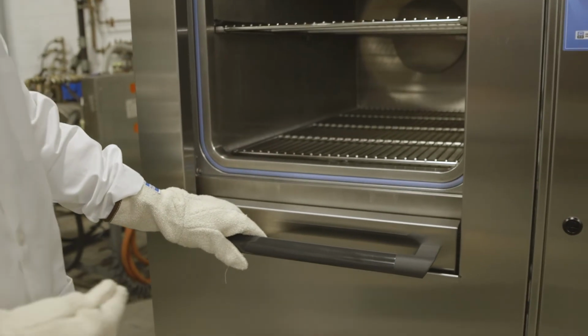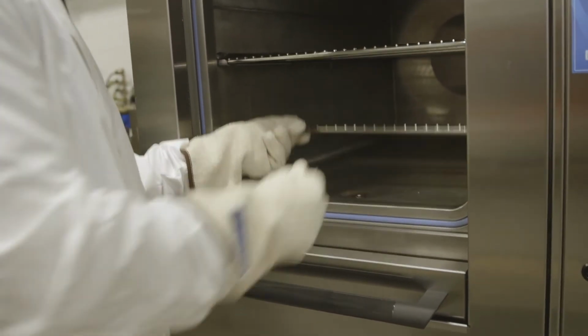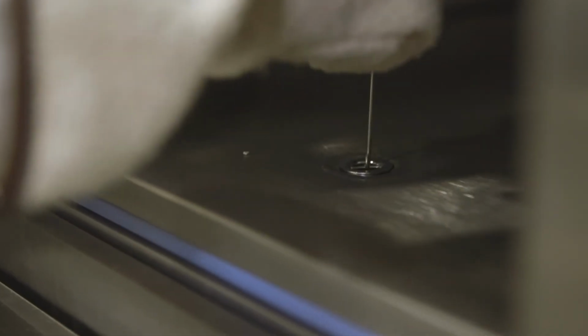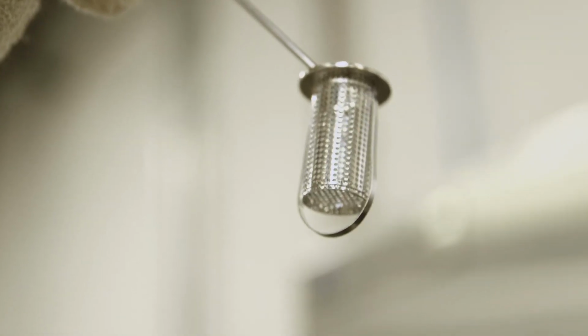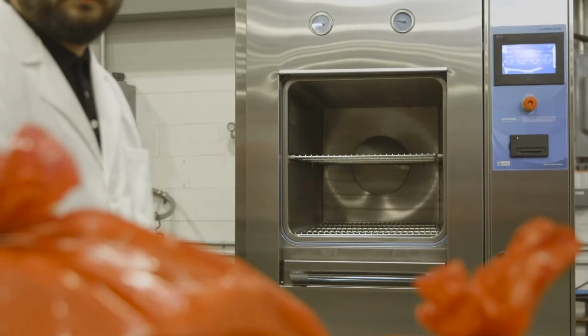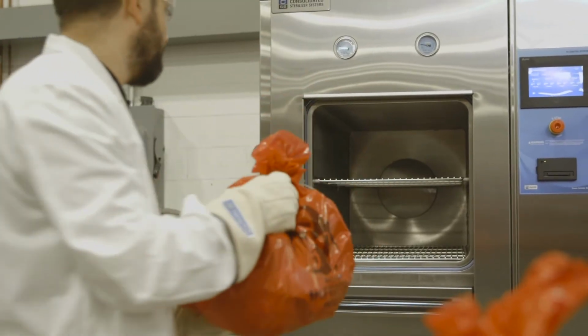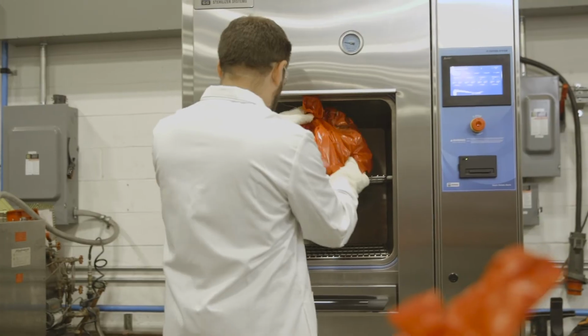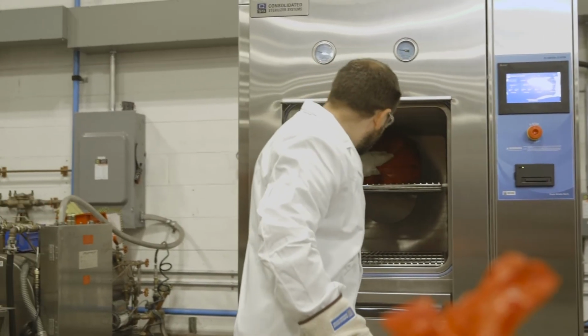Now that you have your protective gear on and have prepared the goods, it is time to load the autoclave. Open the door and make sure that the drain at the bottom is clear from debris, and if there is, empty the drain strainer. This is best done in the morning before the sterilizer is hot. Once you've done this, place the goods in the chamber so that nothing is touching the side walls or bottom floor of the autoclave. Be mindful never to overload the autoclave.